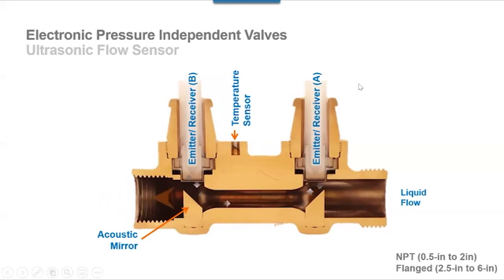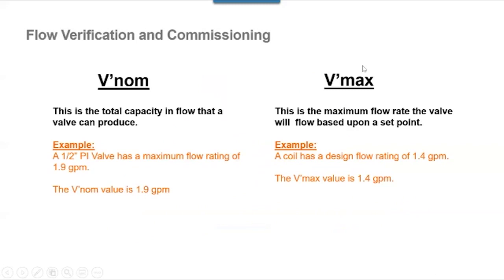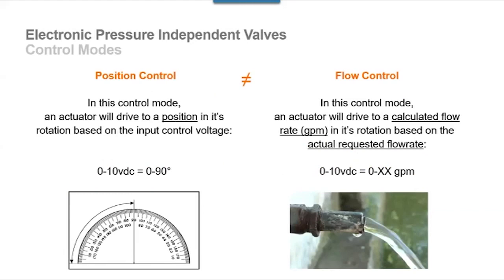You see here again the VNOM and the VMAX. Think about this as we head through some of this other discussion. The electronic pressure independent valves have the capability of being programmed either for a position control, or pressure dependent mode, like a globe valve, and flow control mode, which is a pressure independent mode. Simply put, in position control, if my control signal has a 50% control, let's say I've got a 0 to 10 volt signal, if I go to 5 volts, that actuator is going to drive that valve 50% open, regardless of flow.